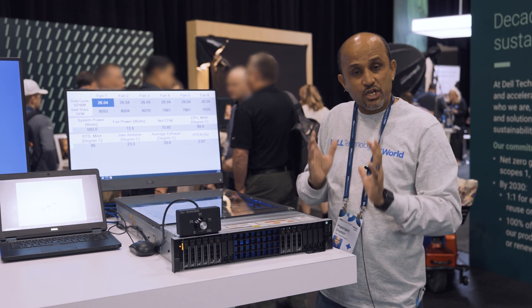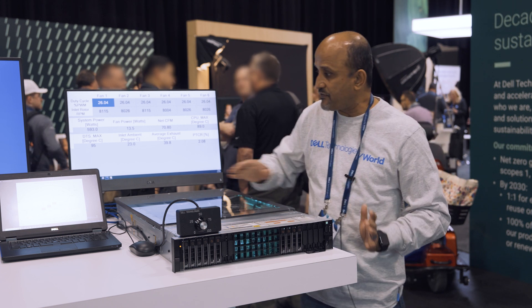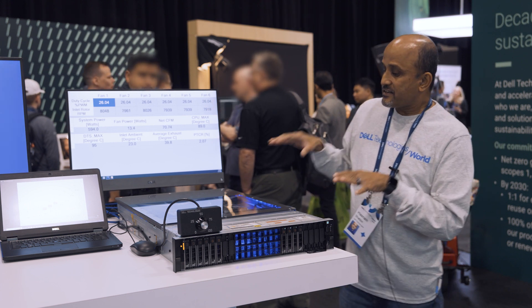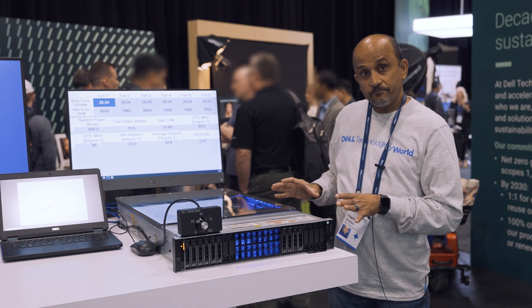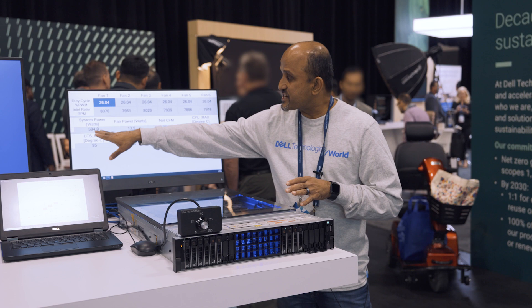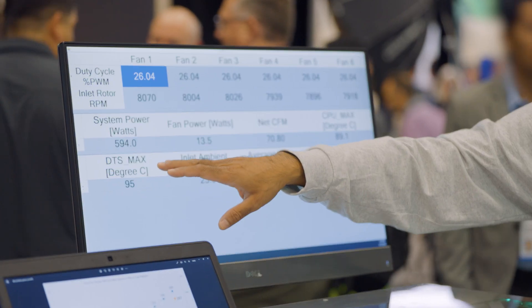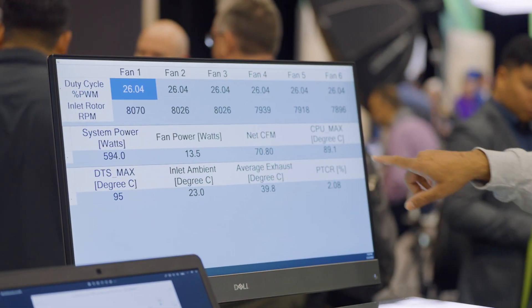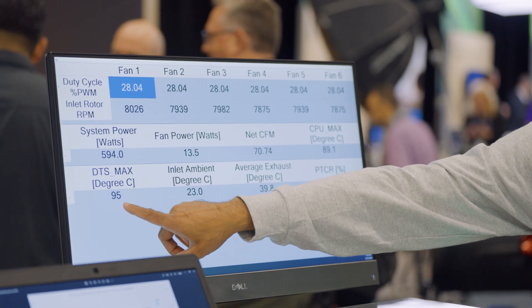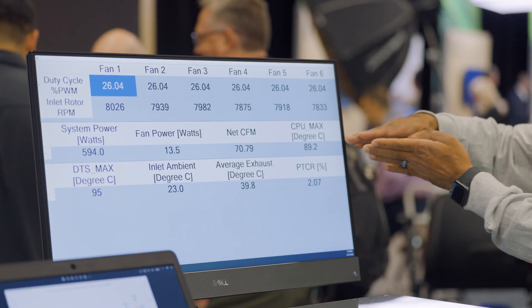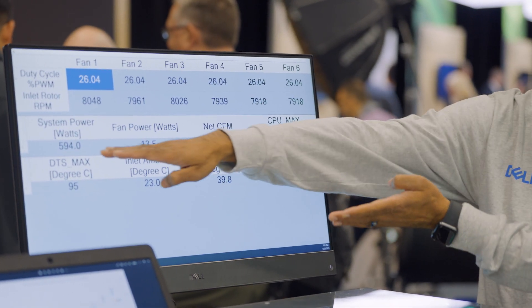If Dell does a good job from a controls perspective controlling the fan to the lowest possible state, we are saving you significant amount of fan power. This system is actually operational, it's running a workload which is approximately 600 watts of system power and the CPU spec is 95°C, so I'm cooling the CPU very close to the spec.